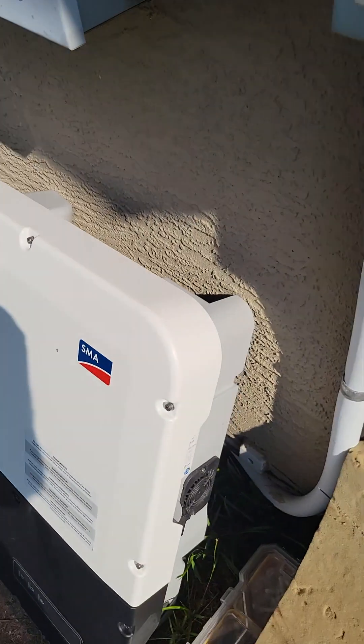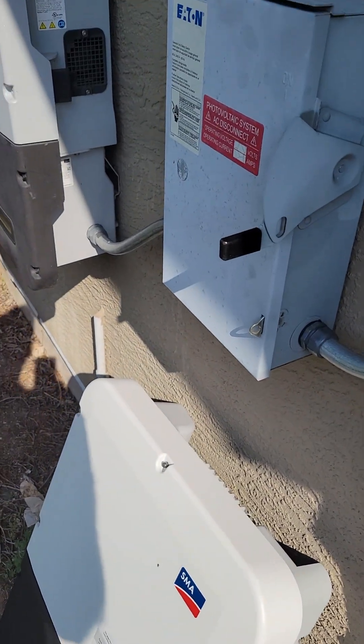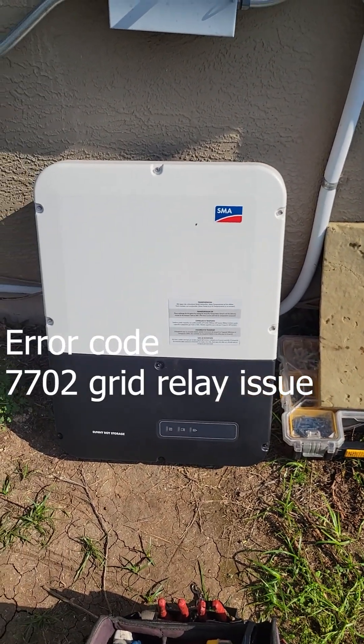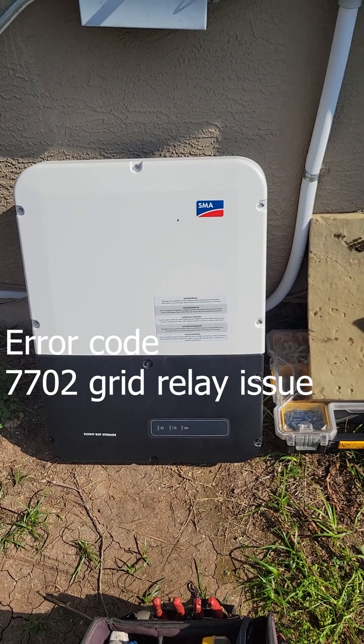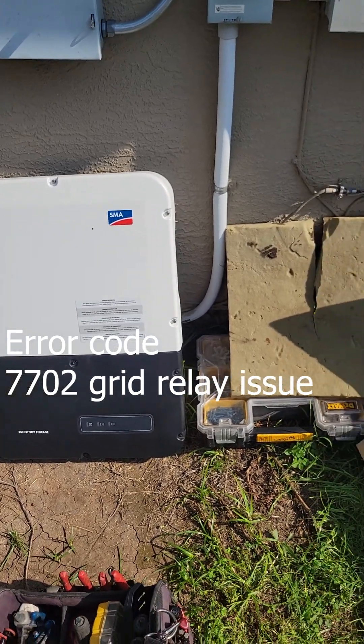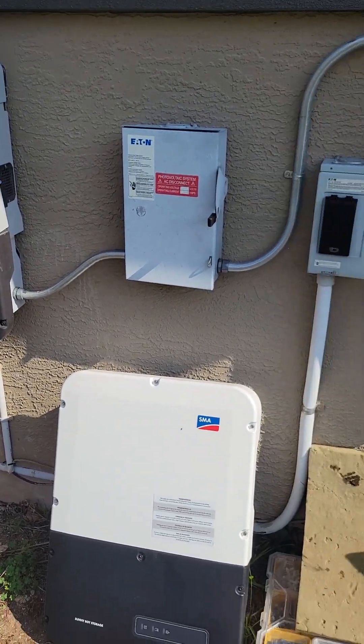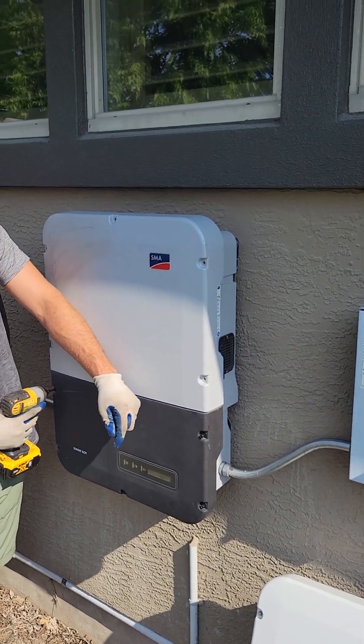Now it's inverter changeout time. We got the DC powered off on the roof. Make sure the serial numbers match - yeah, it's exactly the same SMA SBS 7.7 inverter. There was an SMA failure code I've got to look up, but it was under warranty. The inverter itself - this system was installed by somebody else and we're just doing the replacement.